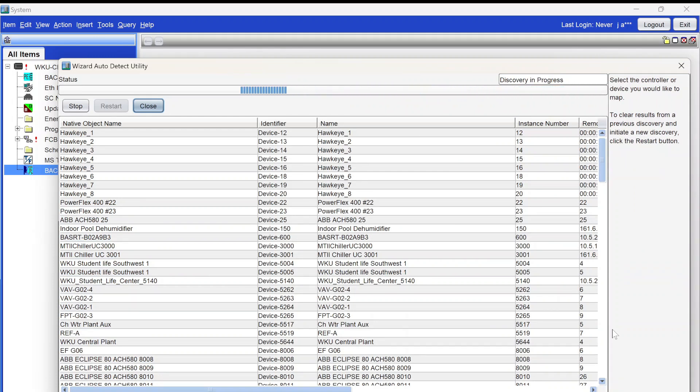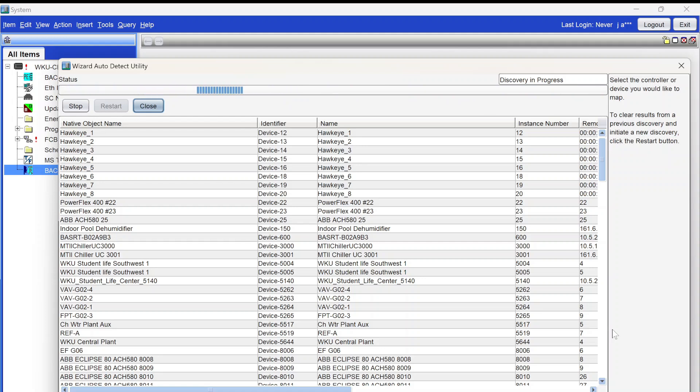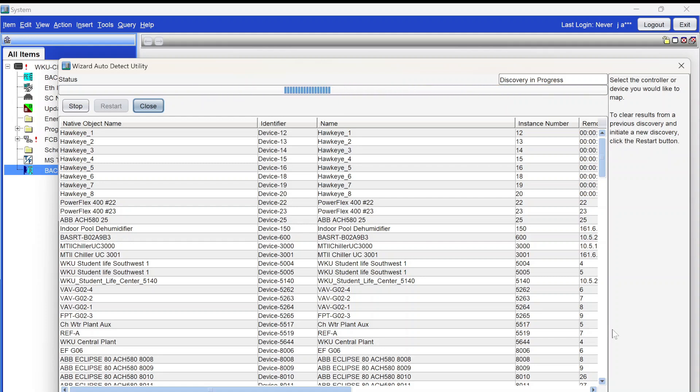Of course, everything is behind a firewall in our system. We do have some pretty tight stuff. But we are now just scanning. It's going to take a few minutes for all of this to get through. Basically what we're going to do, we know what the IP address is for the device, the instance ID as well as the name for that device. So we're going to let this continually run until we get everything populated, and then we can simply select that from the list and add that piece of equipment to our system.